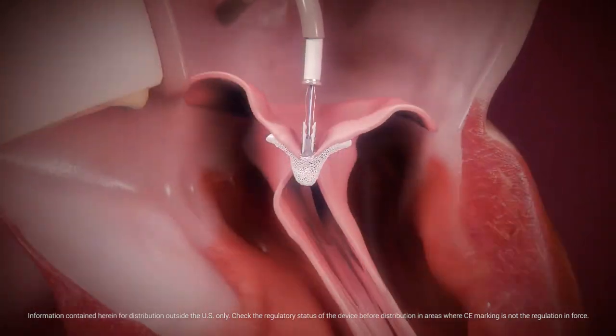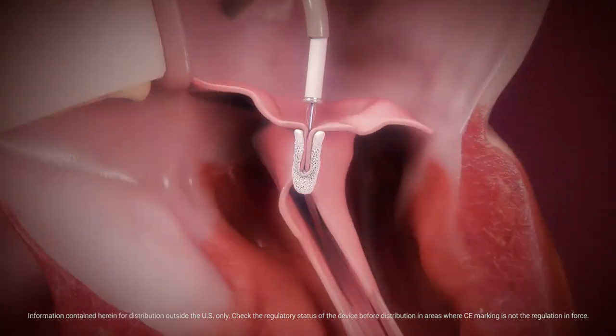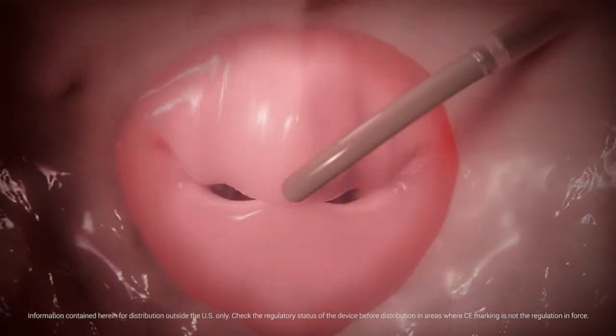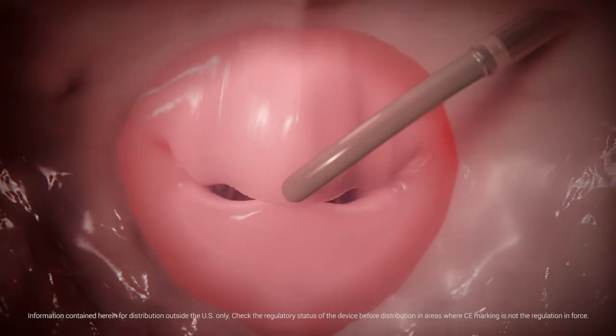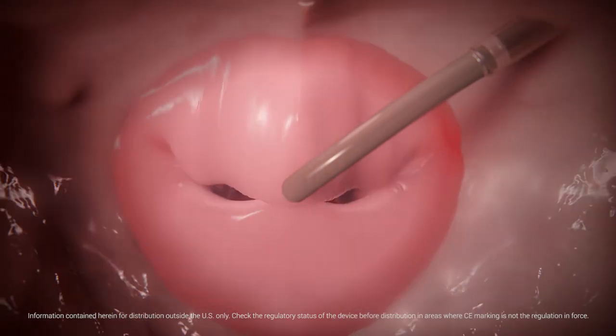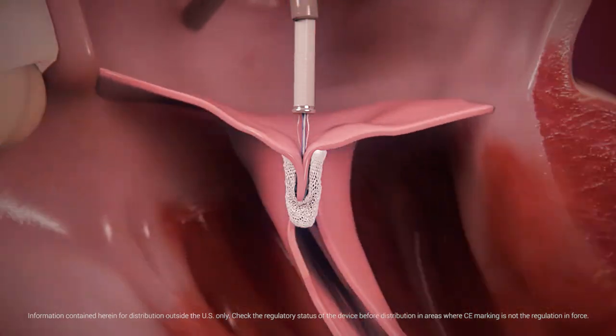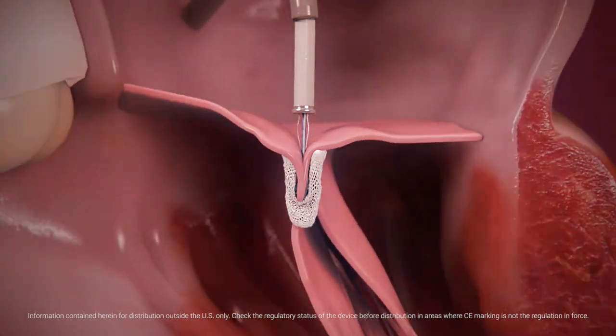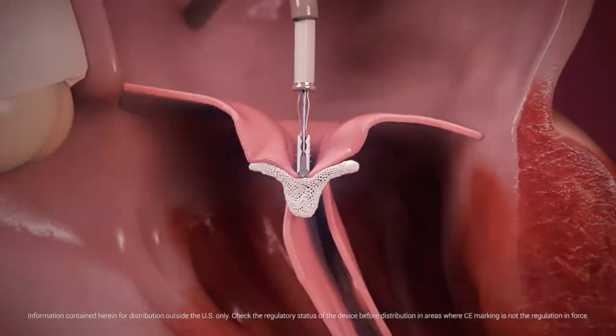MitraClip grippers are designed to drop firmly into the clip arms, securely capturing both leaflets. Once the arms are closed, they create a double orifice within the mitral valve. Prior to clip deployment, echocardiographic imaging is used to assess procedural efficacy and leaflet capture. The MitraClip can be released and repositioned for optimal MR reduction.